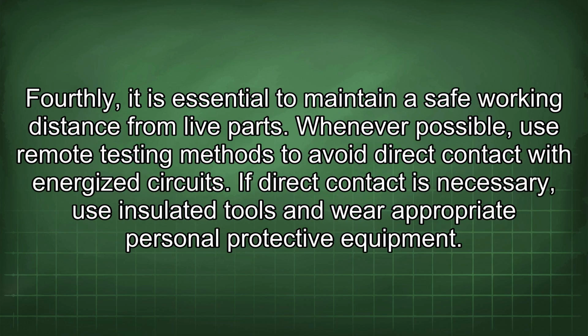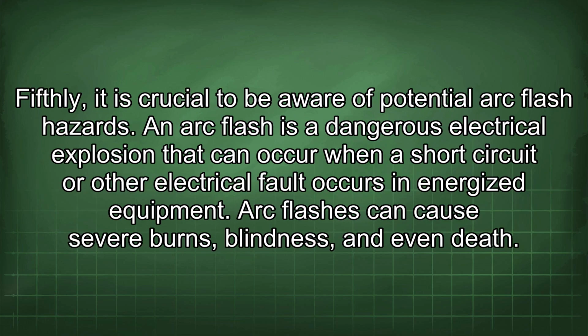Fourthly, it is essential to maintain a safe working distance from live parts. Whenever possible, use remote testing methods to avoid direct contact with energized circuits. If direct contact is necessary, use insulated tools and wear appropriate personal protective equipment. Fifthly, it is crucial to be aware of potential arc flash hazards. An arc flash is a dangerous electrical explosion that can occur when a short circuit or other electrical fault occurs in energized equipment. Arc flashes can cause severe burns, blindness, and even death.